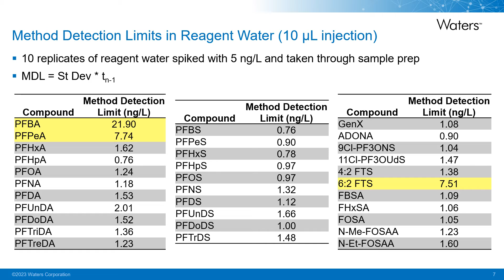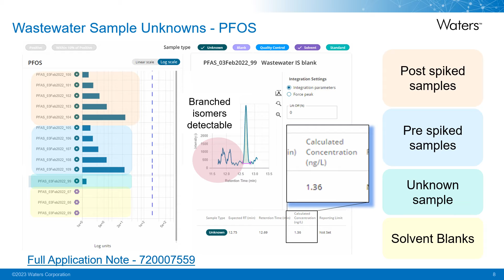Then when we translate into actual water samples, I'm showing an example of a wastewater sample here, again using that direct inject sample prep, which is just a dilution and filtration step. So no real removal of matrix is happening here. In a wastewater influent sample, so prior to any processing of that sample, we can easily detect PFAS in the sample down to 1.36 nanograms per liter, again using that 10 microliter injection volume.